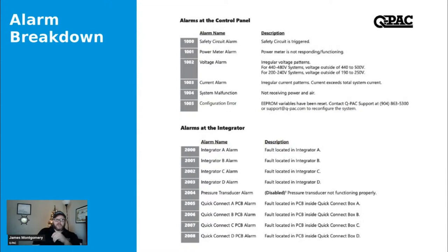Moving on, the configuration error. This one should be extremely rare. These devices are programmed. We actually input this data and then test it before we send you your unit. Stranger things have happened with EEPROM. If you guys remember the deal with EEPROM chips and battery backups, these are variables that we key into the PLC software. And if those variables are lost, then this will be your alarm. It'll not know what voltage it's supposed to be operating at. It'll not know how many fans it's supposed to have. This is something that my team can help you go through to make sure that your configuration settings are correct. If you don't get the alarm, then the assumption is everything we set up is maintained inside there.